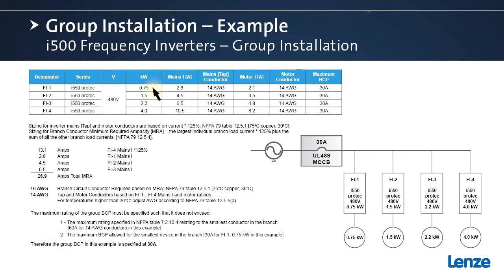In this example, the smallest device in the circuit is the 0.75 kilowatt frequency inverter. That has a maximum branch circuit protective device of 30 amps. So that's the result, is we can use a 30 amp branch circuit protective device for this group. I'll show a little bit more detail of this example in the next slide, but this is the methodology for determining the conductor sizing and the branch circuit protective device sizing.